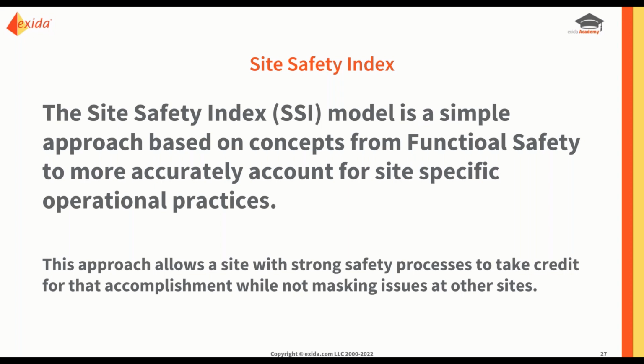I'll come back to this in a minute, but I talked about operational and maintenance characteristics. One of the reasons I'll hit that again is that a lot of reliability engineers have never imagined that the failure rate is different from site to site. But as I said, the failure rate can vary by 4 to 10x. That's a big deal, maybe the most significant variable of all.